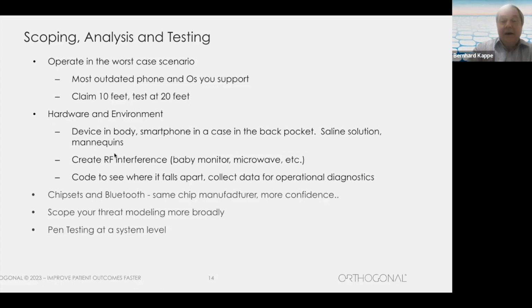If it's in home use, you want to create RF interference and test things like baby monitors, which may be really polluting in the environment, microwaves, etc. What is a typical home environment actually like? Those are the kinds of things you'd want to test. And similarly, in a clinical setting, you'd want to look at those things as well. And again, if you have enough patient risk here, put some code in there to see where things fall apart and collect data for operational diagnostics, at least when you're doing internal testing. You may not be able to have that in your production applications, although in some cases you might.